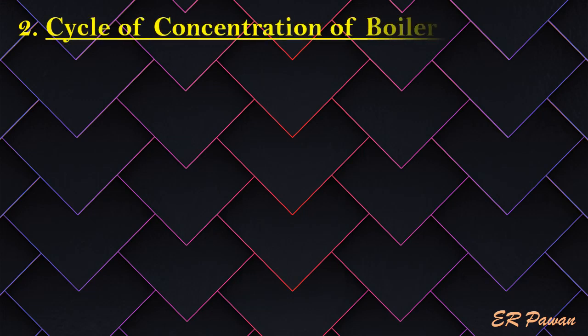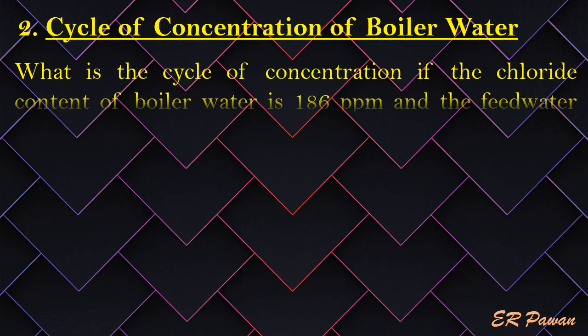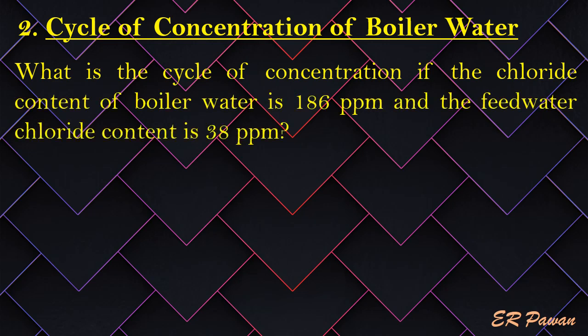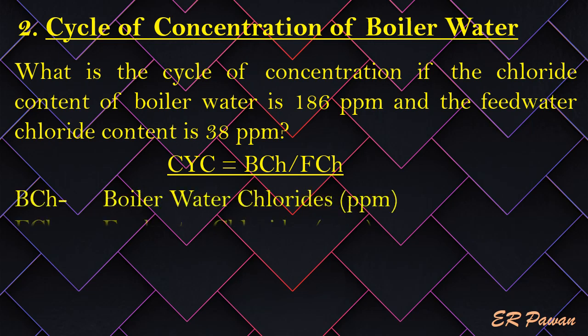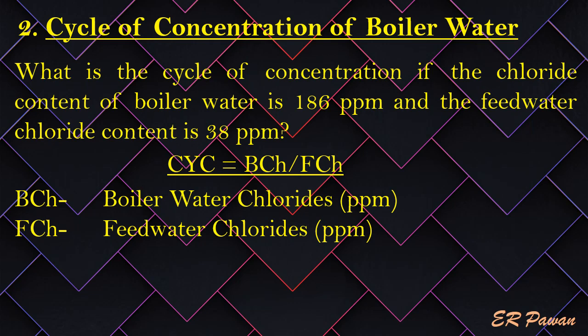Formula 2 — Cycle of Concentration of Boiler Water. What is the cycle of concentration if the chloride content of boiler water is 186 parts per million and the feed water chloride content is 38 parts per million? CYC equals BCH divided by FCH. Where CYC = cycles of concentration, BCH = boiler water chlorides (ppm), FCH = feed water chlorides (ppm). Let's put the value in the formula.